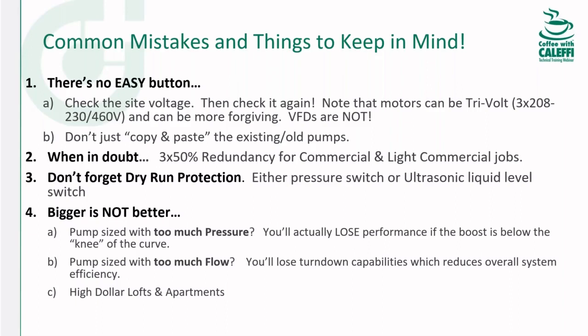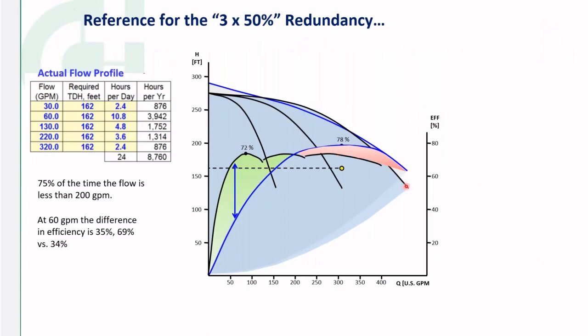And maybe a final thing is bigger is not always better. If you size pumps that have too much pressure, you're actually going to lose performance if the boost is below the knee of the curve. And by the knee of the curve, I'm talking about this point right here. If you're wanting to use 400 GPM, but the pumps are only boosting 100, or you thought they would be boosting 170, you're going to be out past the shaded area and possibly cavitating and in overload conditions.